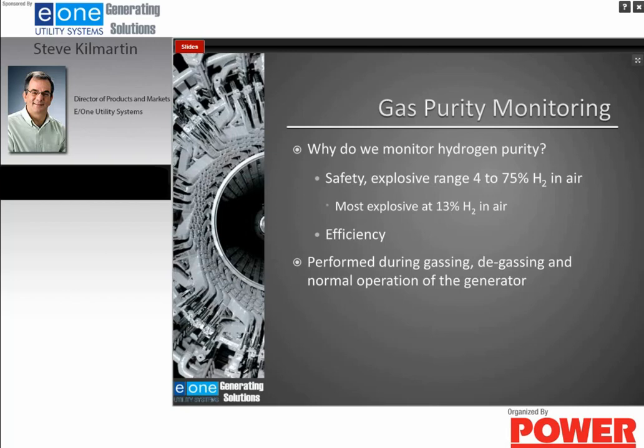And we also want to measure the hydrogen purity because of efficiency. The purer the hydrogen, the less windage loss that you have, so that you can generate more megawatts. You typically, on a generator that has vacuum-treated seal oil seals, would like to keep the hydrogen purity at approximately 96% or higher. We also monitor gas purity during the gassing and degassing of the generator, or purging of the generator. And we also monitor the hydrogen purity during the normal operation of the generator.